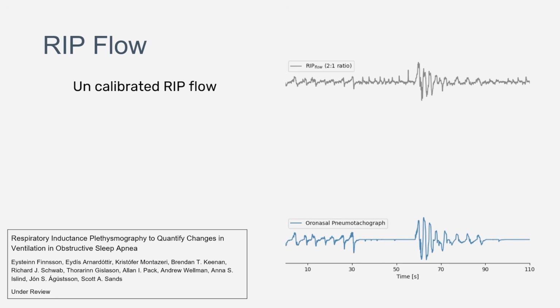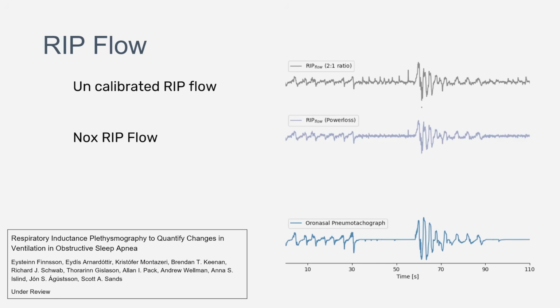And the reason for this is that if you just add the signals from the abdomen and the thorax together, they don't cancel exactly during the apnea, so you have this residual movement. We have introduced a calibrated RIP flow in our product. And when you do the calibration, so this is calibration that just runs over the night, you don't have to do anything special, you get a better visibility of the apnea, but there is still a little bit of fuzziness in the signal.